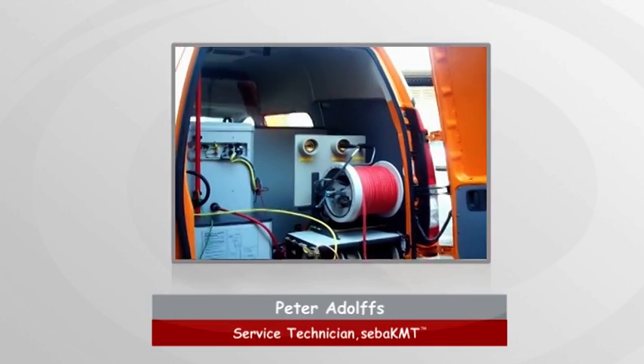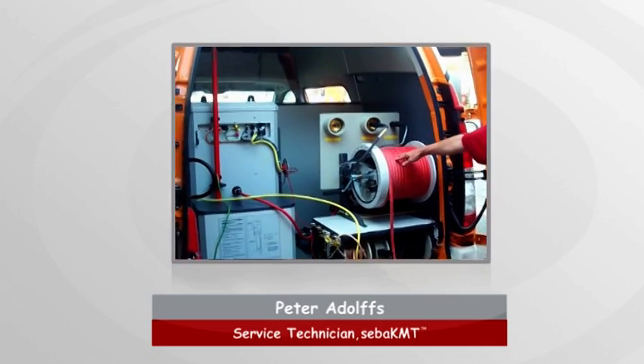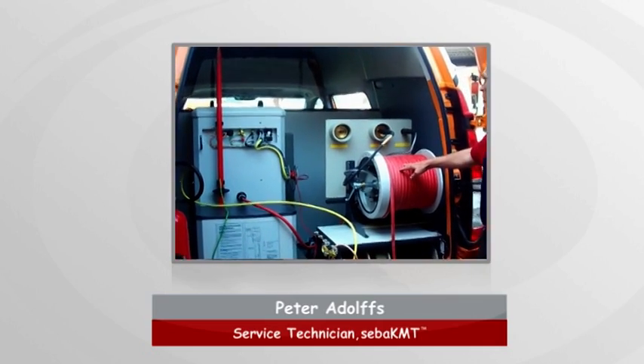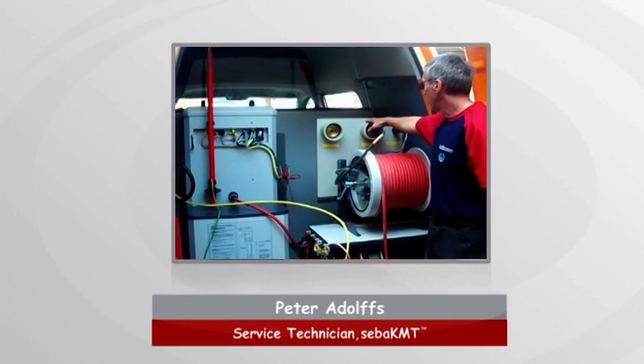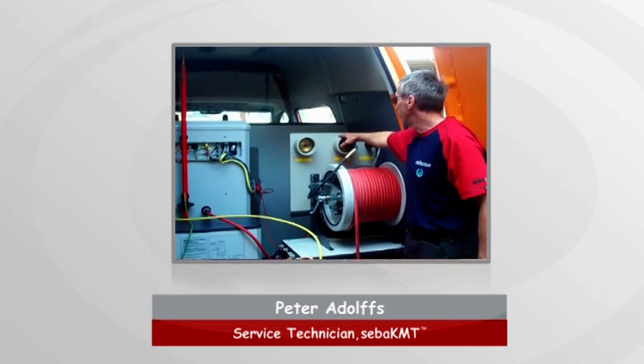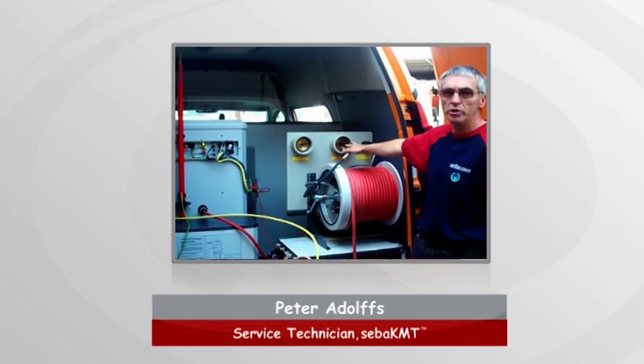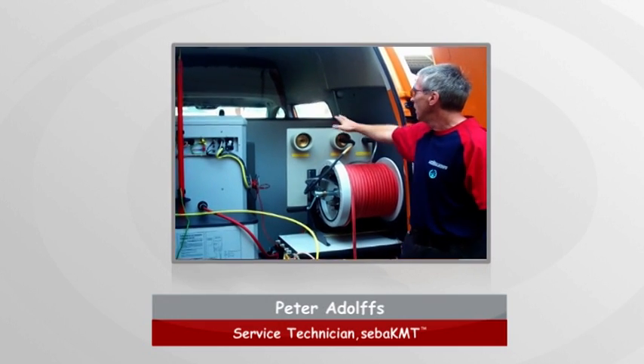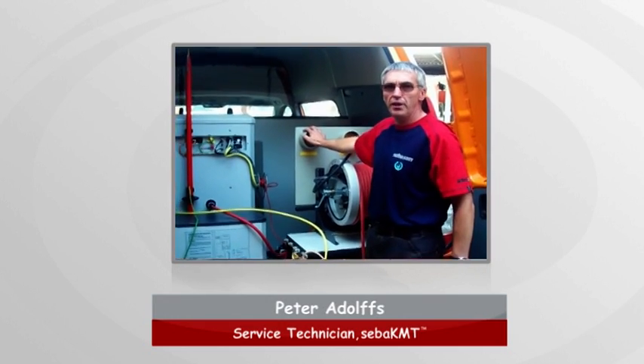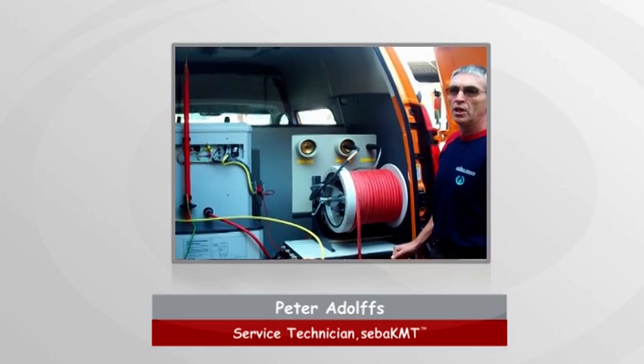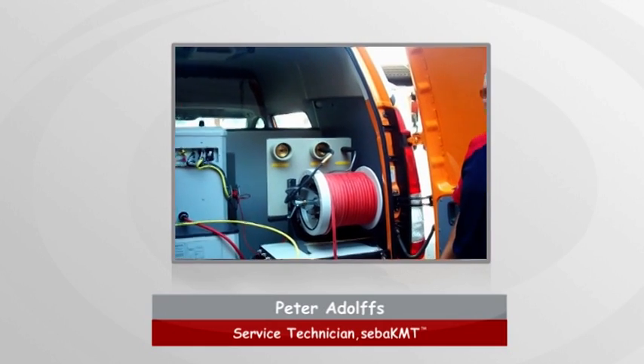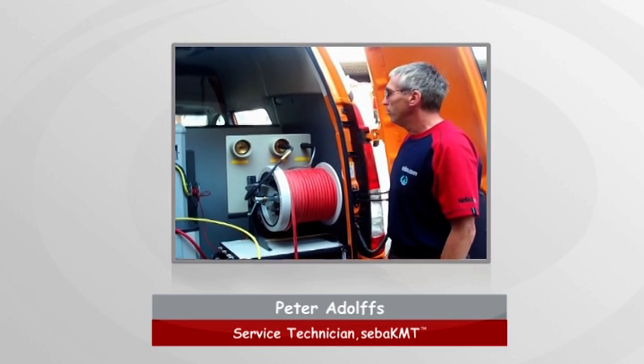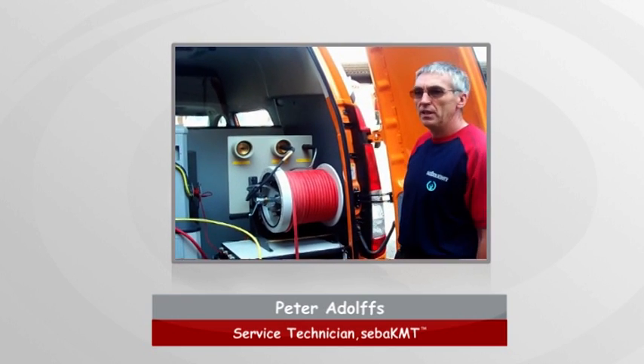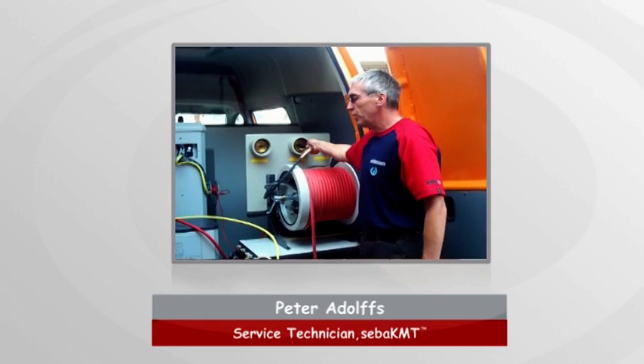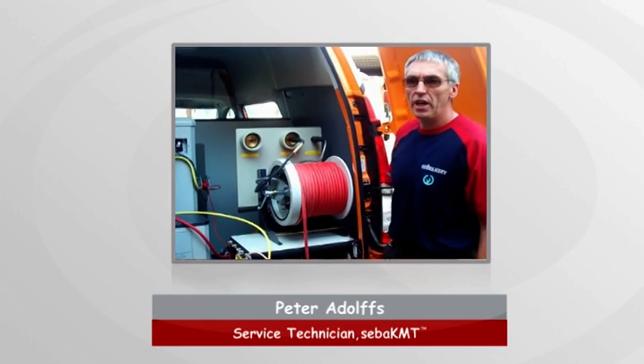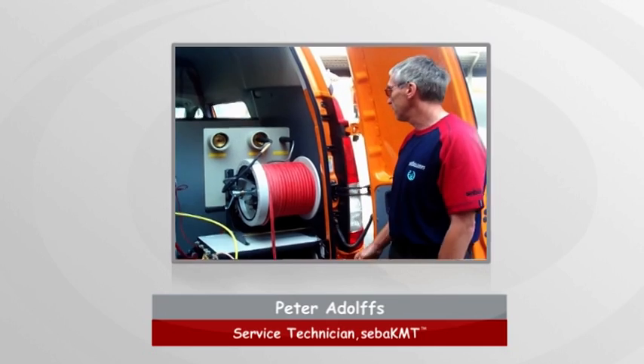The next step is our high voltage cable drum. We have two outputs of our system. One is from the SPG40, for pre-location, pinpointing, sheath testing and so on. The other one is VLF, very low frequency, a test unit for DC test, VLF and sheath fault location also. So when we arrive at the cable fault, we first start with SPG40 mode to check where the cable fault should be and so on.